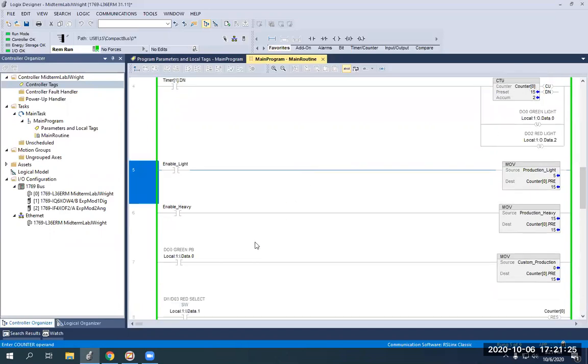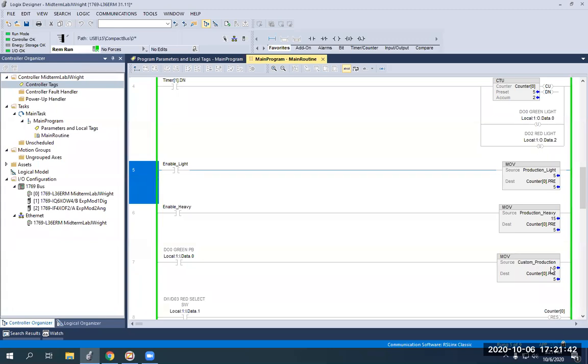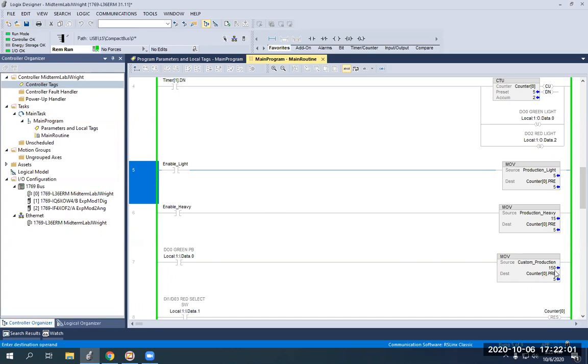So we're essentially using buttons on the HMI. These three button or these two buttons here on the HMI. To move five or 15 into our counter preset. I'm going to make it, I'm going to hit run light again. Now we're at five again up here. So now our custom production is still at zero. So say I hit my run custom on my HMI. And I type in 150. And then enter. See how that 150 changed over here without me having to do anything in the PLC program is because I did it on the HMI. Now I have to hit my green push button to move that 150 into my counter preset. Watch up here on my counter zero. Hit the green button now. It changed to 150.